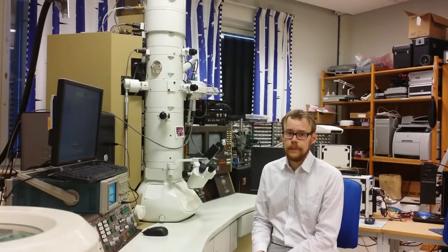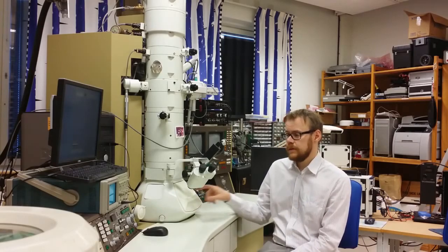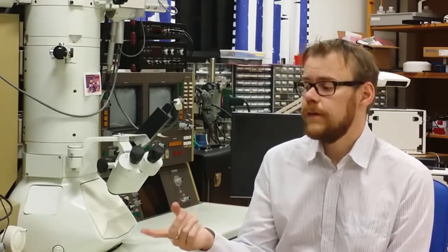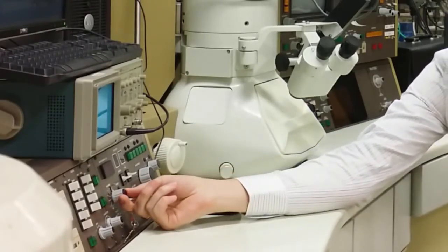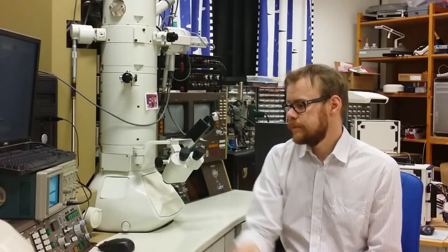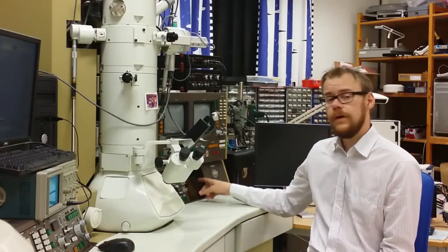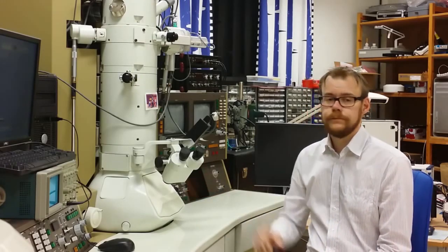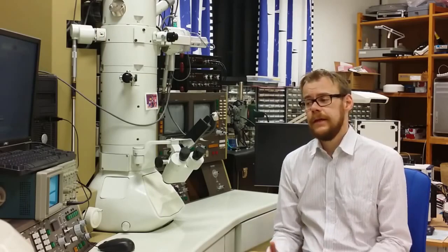Now I have turned on the lamp again and put back this protective cover screen. So how to shut down the microscope, you basically do the reverse procedure of starting it. So first you turn off the filament. After that you go down to the 150 kilovolts in accelerating voltage. Then you turn off the high voltage. Turn off the computer screen. And that's it.